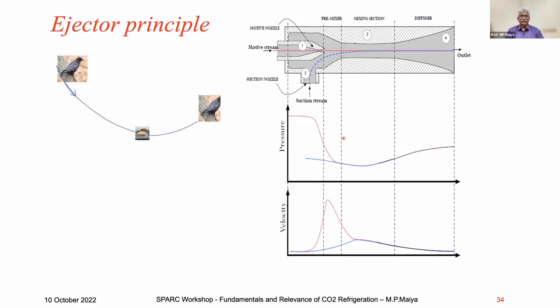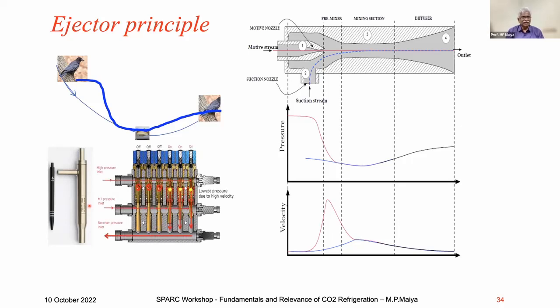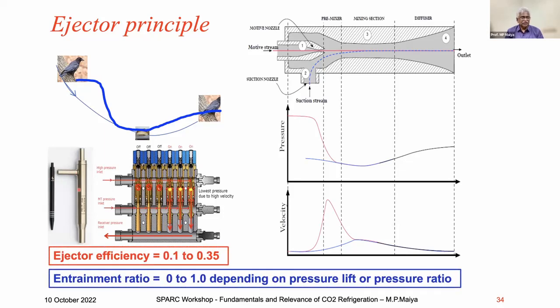You can see, as a layman, this pictorial. Without flapping, this bird takes this food, and without flapping, it goes to a higher level. Pressure, height, converted to velocity, and it goes to a certain height with this load. So this is the single ejector. Yeah, the ejector pack. You can see the size. Of course, this will be a little bigger. This is a single ejector, and for ejector efficiency you can get 0.1 to 0.35. You can't have 1 because there are mixing losses. Though there is no thermodynamic limit, it is limited to this.